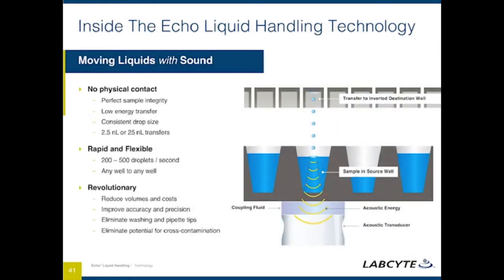At the heart of the Echo Liquid Handler is an acoustic transducer, and that's depicted at the lower right-hand side of the slide. The acoustic transducer is responsible for generating the acoustic energy. It also serves the function of focusing that energy at the surface of the fluid being transferred. We have a coupling fluid that enables the acoustic energy to travel from the transducer into the particular fluid that we are transferring. And in doing so, we can generate droplets of either 2.5 nanoliters or 25 nanoliters and eject those from a source well up into an inverted destination well.